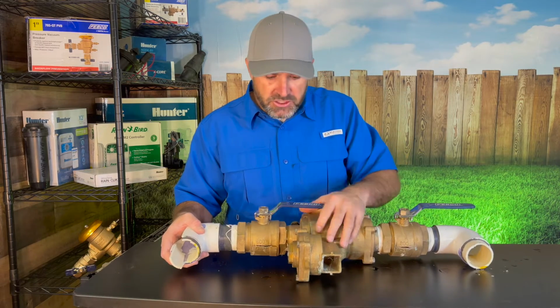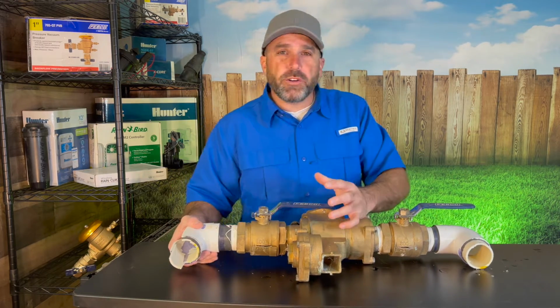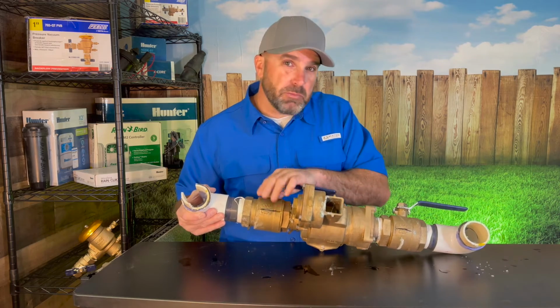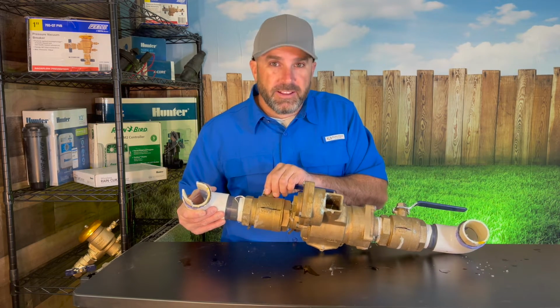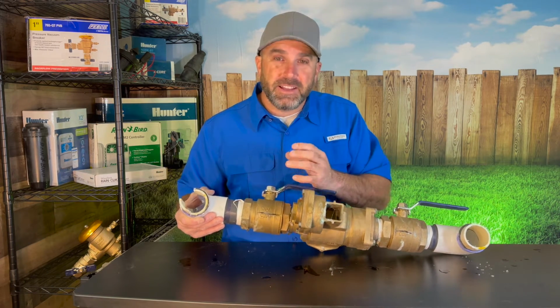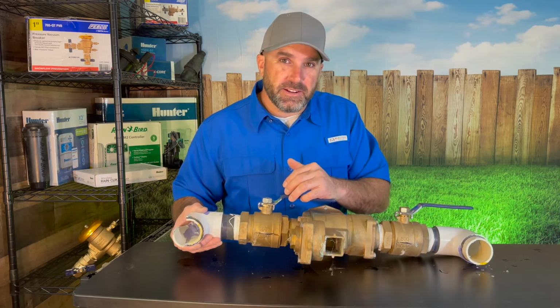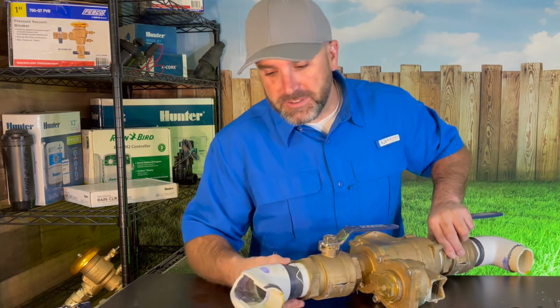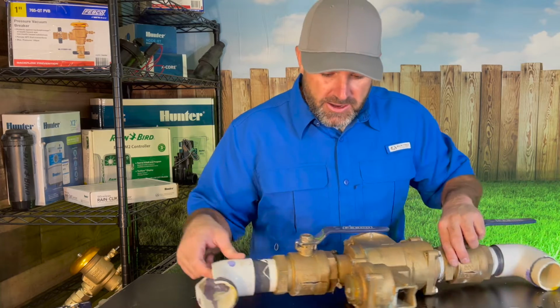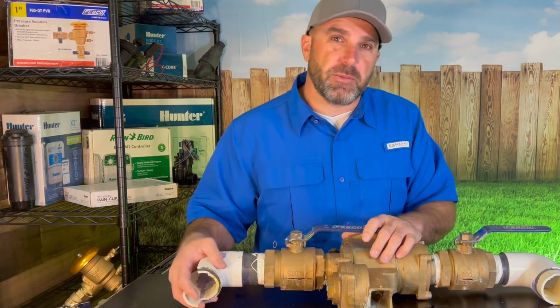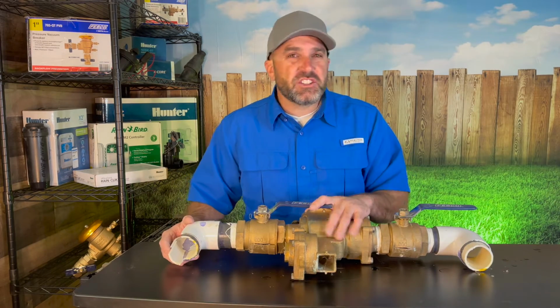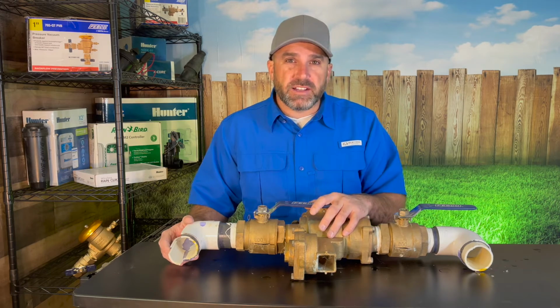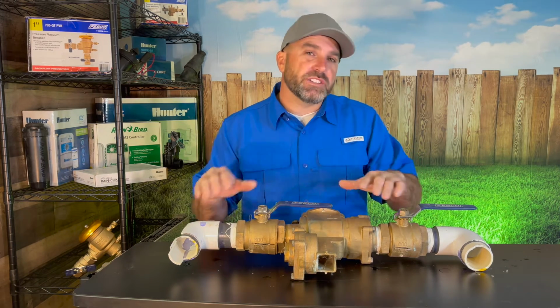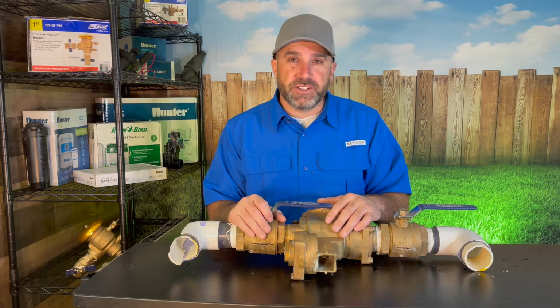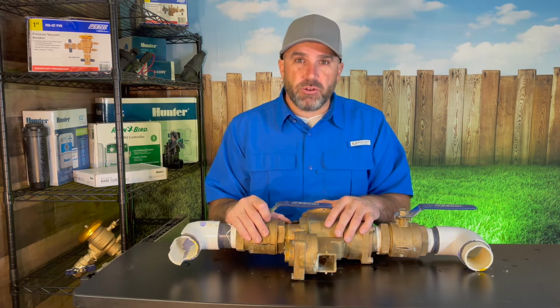Now this is pretty tough stuff. And for water to freeze and be able to break this metal bronze material lets you know the force behind that water freezing and expanding. You may expect it to do that on a plastic PVC, but it will actually do it on this metal part too. So this is a good example of what happens to a backflow device that's installed above grade, and when it's not winterized at all and you've got a lot of freezing weather, it's going to crack and break it.